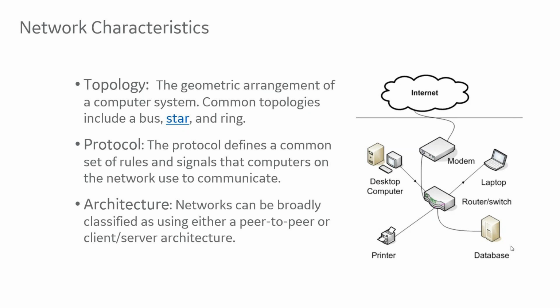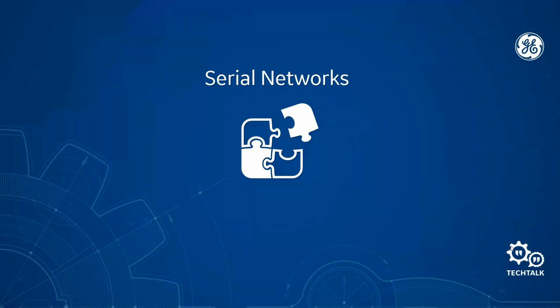There are basically two architectures: peer-to-peer, or one-to-one, connecting one device directly to another; and client-server. For example, your server could be a SCADA system that needs to connect to a number of devices in your substation to get information. This is usually called client-server, master-slave, or one-to-many—same acronym for that type of architecture.